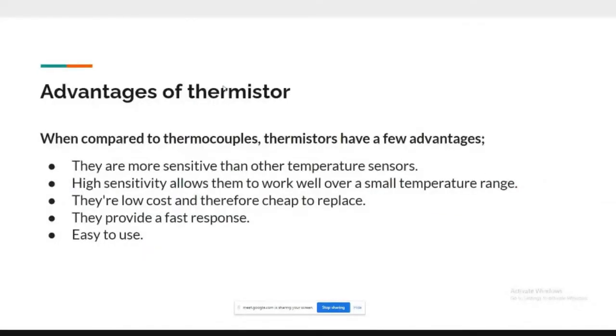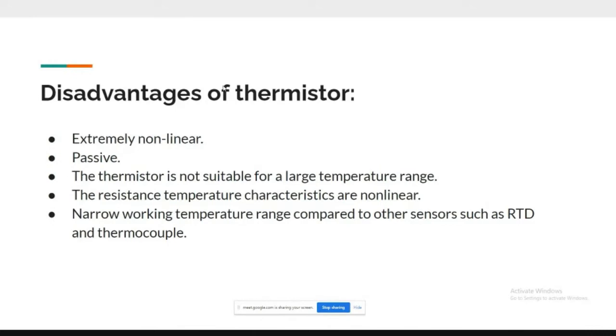Advantages of thermistors: when compared to thermocouples, thermistors have a few advantages. They are more sensitive than other temperature sensors. Being highly sensitive allows them to work well over a small temperature range. They are low cost and therefore cheap to replace. They provide a fast response and are easy to use. Disadvantages of thermistors: extremely nonlinear, passive. The thermistor is not suitable for a large temperature range. The resistance temperature characteristics are nonlinear, and the working temperature range is narrow compared to other sensors such as RTD and thermocouple.